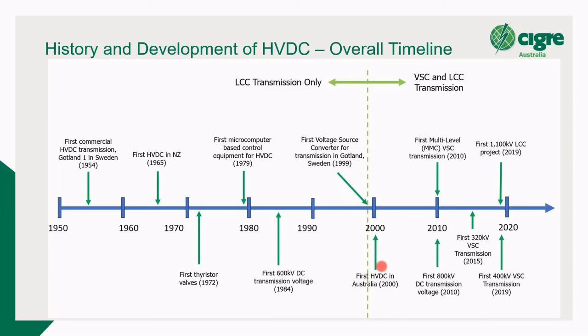And then the technology has pretty much grown. The first 320 kV VSC was installed in 2015. Oops, sorry, I forgot this one. The first multi-level VSC was commissioned in 2010. And now, as far as what's commissioned, VSC is commissioned to plus or minus 400 kV. And there are 525 kV and possibly 600 kV projects under development or close to completion. There's also a point up here about the first LCC project, 1.1 million volts in China.